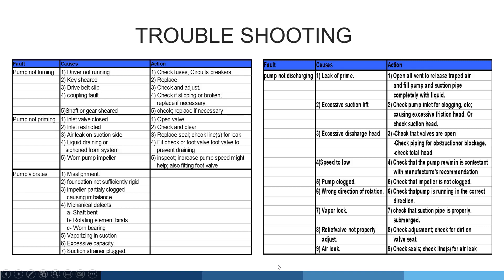If you review this troubleshooting guide, the major causes of pump failure are air lock, suction side clogging, or electrical failures. Always attempt the easiest checks first, then move step by step through the troubleshooting method.